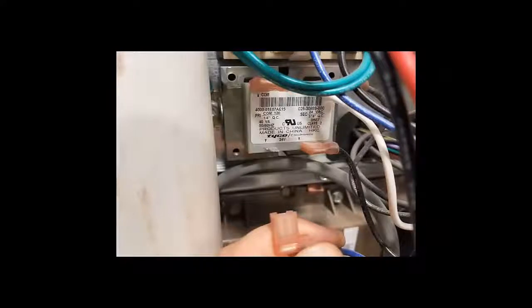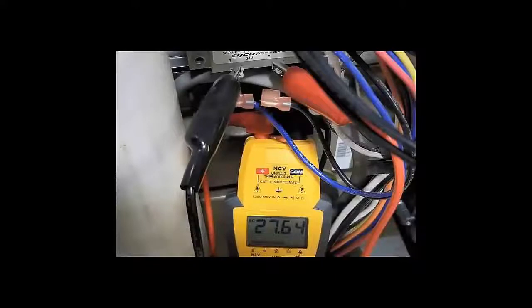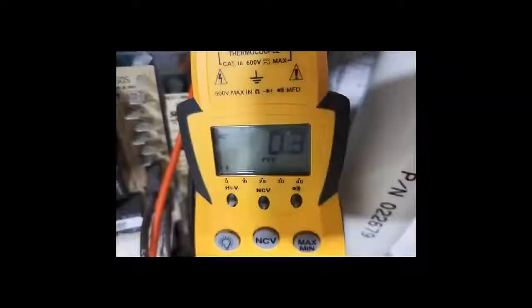Once you're certain you have correct voltage to the transformer, you can reconnect the line voltage wires back to it. Now again, make sure the main power is turned off while you're doing this. And now you can pull the secondary or low voltage wires off the transformer. And this time hook your voltmeter leads directly to the terminals on the transformer. Now turn the power back on. And if the transformer is good, you will read 24 volts plus or minus 3 or 4 volts. If the transformer is defective, you will read 0 voltage on the low voltage terminals.